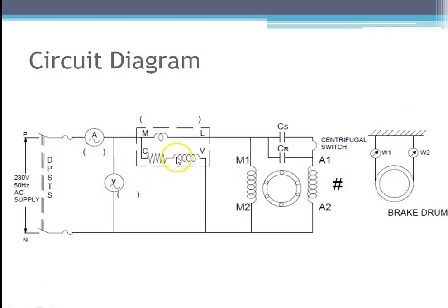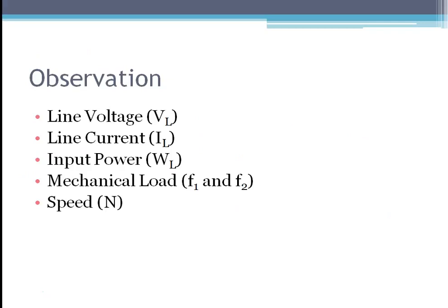The load torque should always be zero initially. If it is not, take it as an error value. After taking the no-load reading, add load by slowly tightening the brake drum, thereby adding mechanical load to the motor. For each addition of load, take another set of readings.